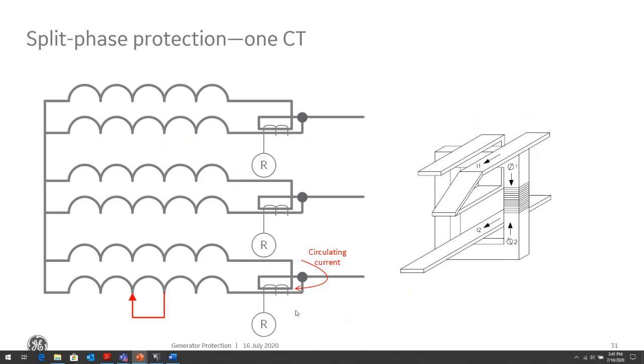So one of the ways we'll be able to detect that is using split phase protection, or one CT, and that CT is installed similar to a core balance CT, where the circulating currents are added into that CT connection, and then the relay sees an overcurrent.